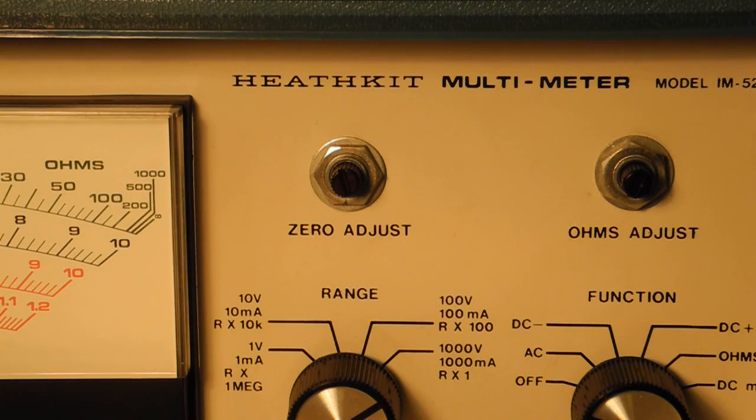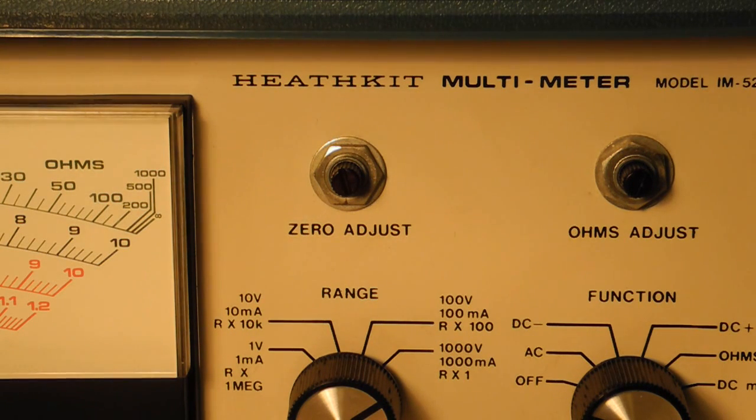The zero adjust knob needs to be adjusted so that the meter reads zero with no input. Typically, you only need to adjust it once and it applies to all functions and ranges. It may need to be adjusted periodically as the batteries run down. The ohms adjust knob is adjusted so that the meter reads full scale when the test leads are open on the ohms function. It also typically only needs to be set periodically.